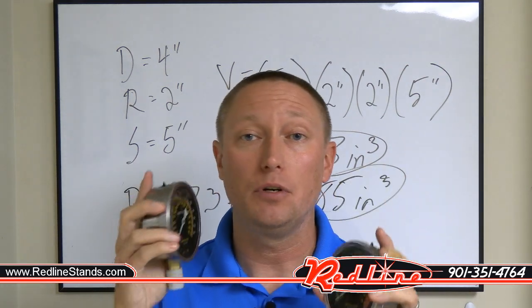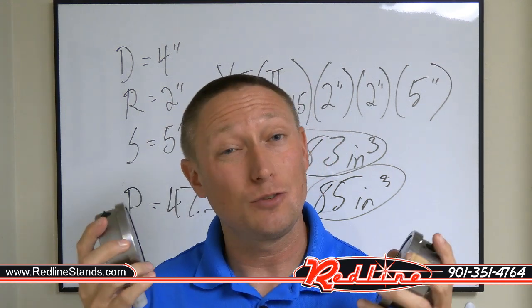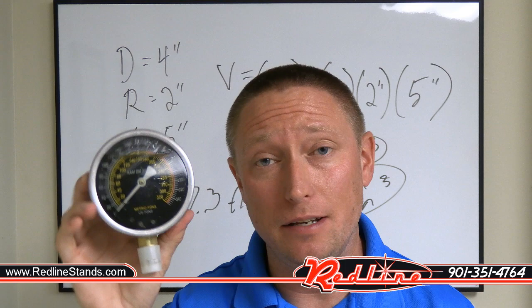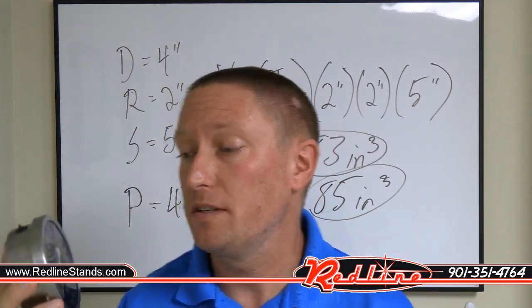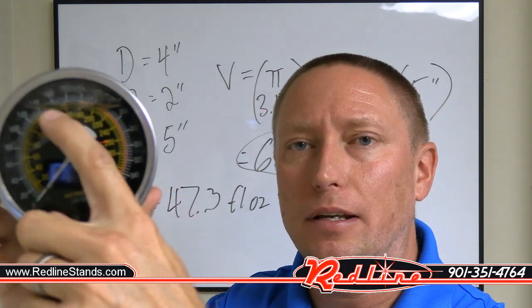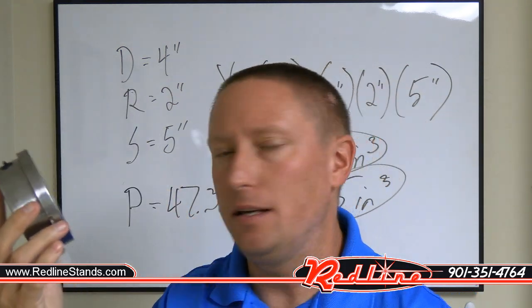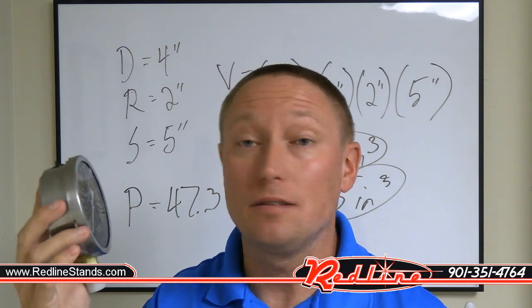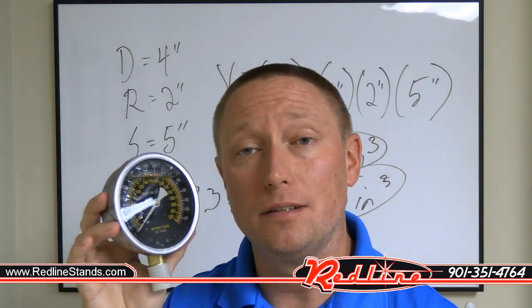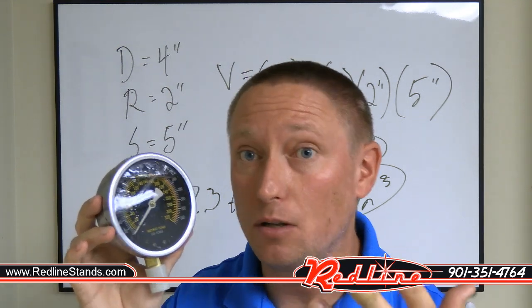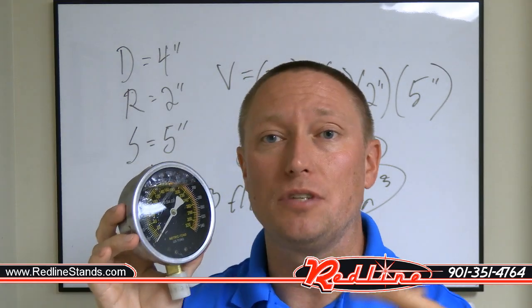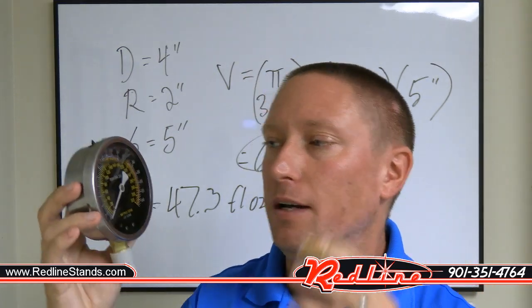Go back and check out the Hydraulics 101 video — it explains pressure equals force over area, which will make sense of why you can't take one of our gauges and put it on just any cylinder. Also, something that happens quite a lot: folks will reach out and say the fluid level in their hydraulic gauge is low, thinking the gauge is leaking. A lot of folks don't understand that that fluid only keeps the needle moving slowly, so if you release pressure fast the needle doesn't shoot back and uncalibrate itself. It's not supposed to be full of fluid.